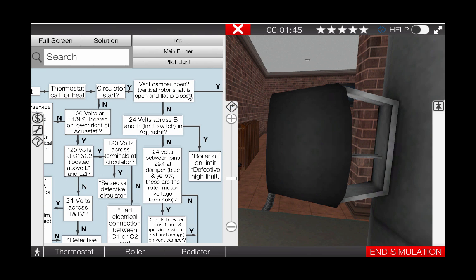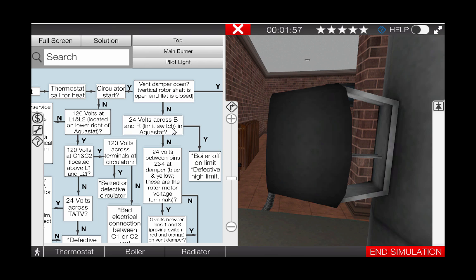Referring back to the troubleshooting flowchart, we can see that after verifying that the damper shaft is in the flat position and the damper is open, our next step is to check for 24 volts across the B and R terminals in the aqua stat. This verifies that the high limit switch is in fact closed.